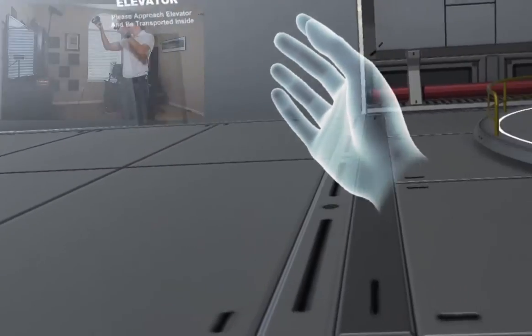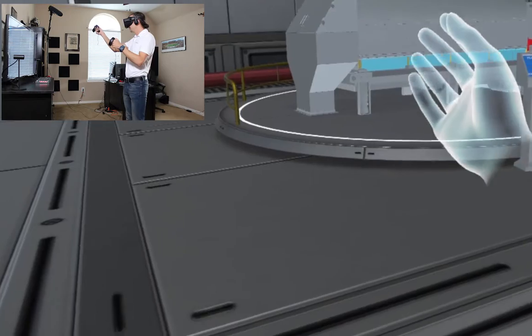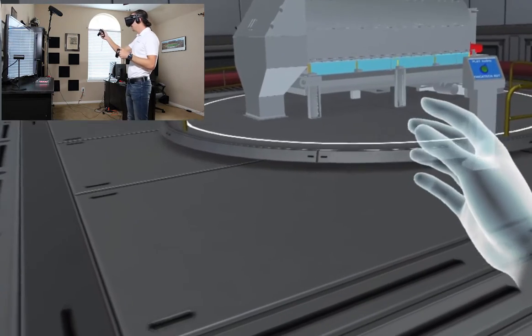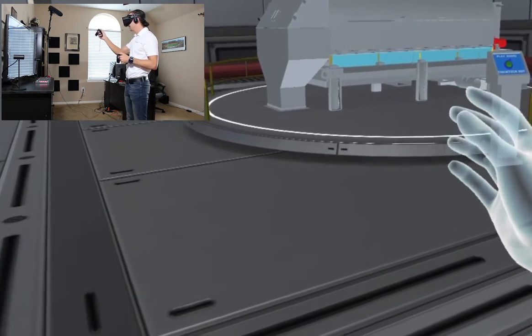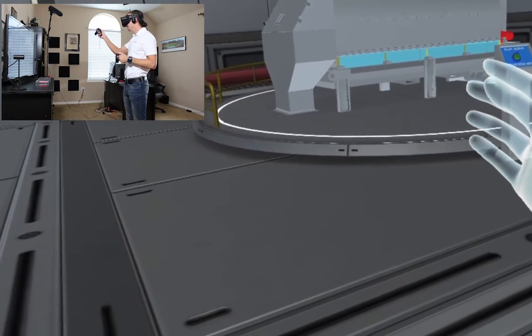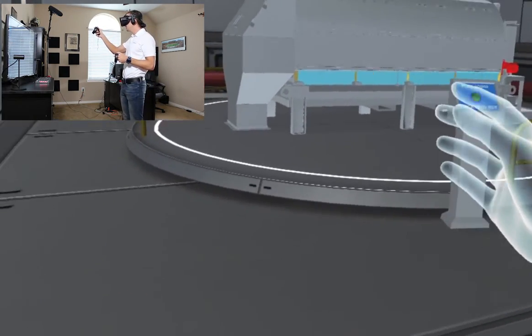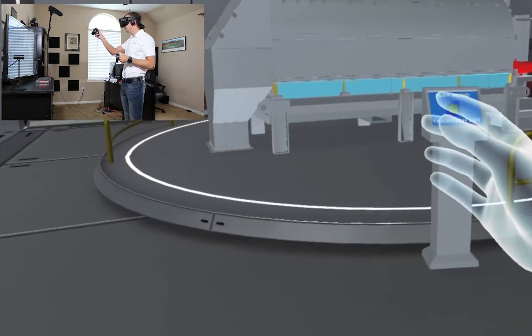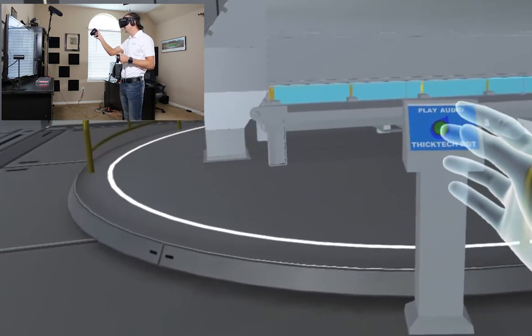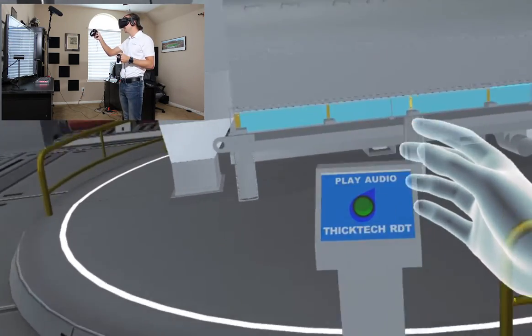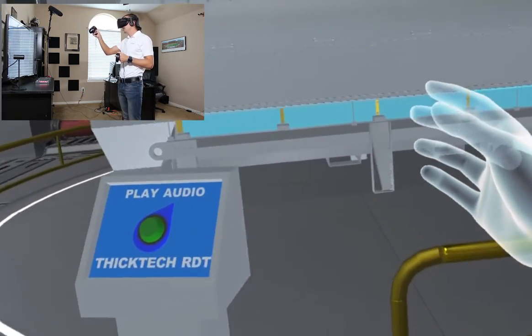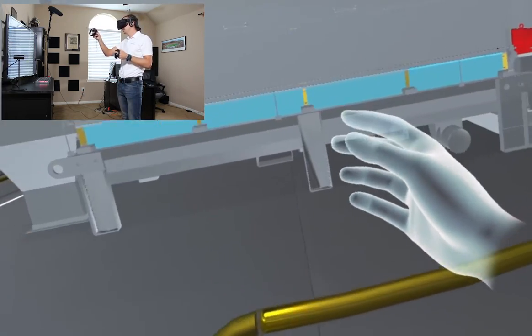Here we are in Parkson's virtual showroom, so let's head over to the ThickTech Rotary Drum Thickener. Thickening is a process where we're taking sludge that's typically between 0.5 to 1% solids and moving it up to around 5 to 8% solids.